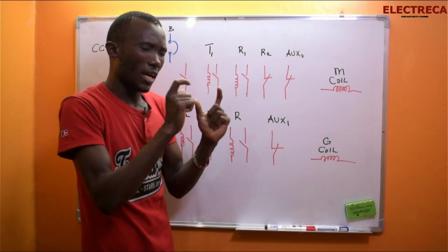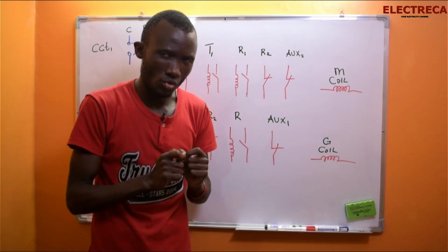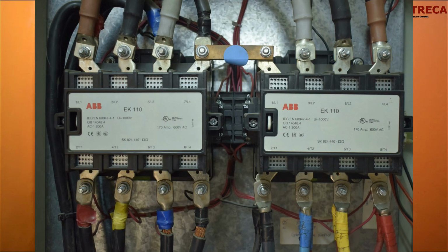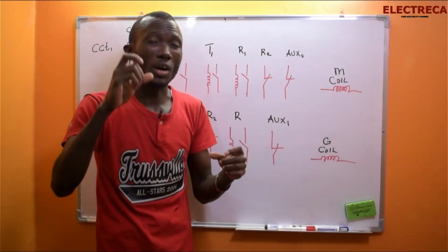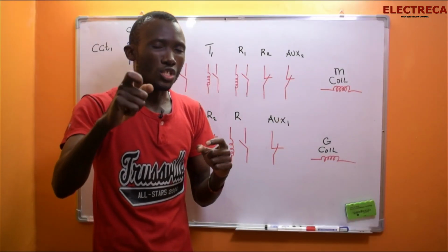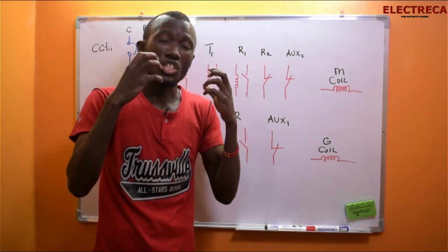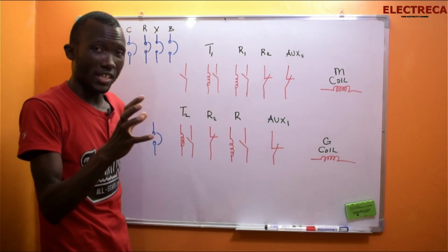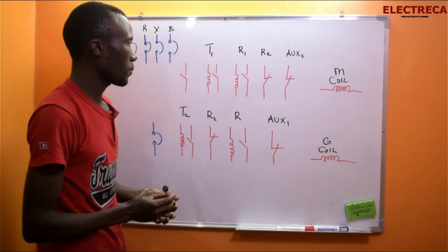We have this control circuit of a changeover switch, and this is a three-phase changeover switch. So you have two sources of power. You have your main utility supply and you have your backup generator, which should start in case your main power supply fails. Right here we have two circuits which are not complete. We will complete them together.